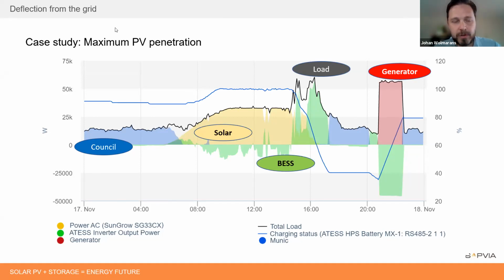Here you can see at night, starting on the left at 12 o'clock, the battery starts off at an arbitrary state of charge. The black line is the load, which we cannot affect, but we can affect which energy source this comes from. You can see the energy draw from council decreases as the solar picks up in the morning at about 5 a.m., and during the day we're supplying the facility almost entirely off solar. Any excess solar, which is the green going beneath zero, is energy that gets charged into the battery energy storage system.